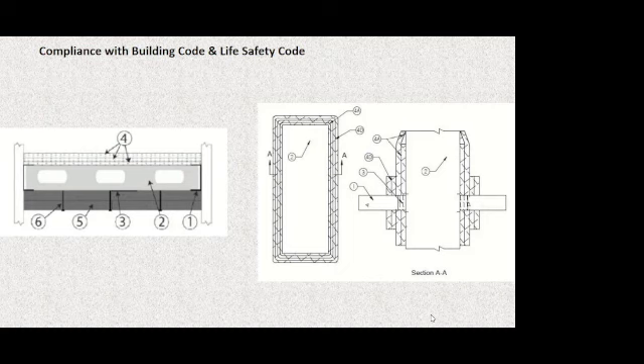So we have to guard against this. This is the importance of the inspection side of enforcement. This is the importance of due diligence and construction administration on the design team during the build process, because we don't always have good actors out there putting in these life safety systems. But I assure you, if we put in less than the fire rated design for the protection of the life safety HVAC systems in a building, we're doing exactly the same thing. It's settling for the mere appearance of fire resistance, which is worse than nothing at all.